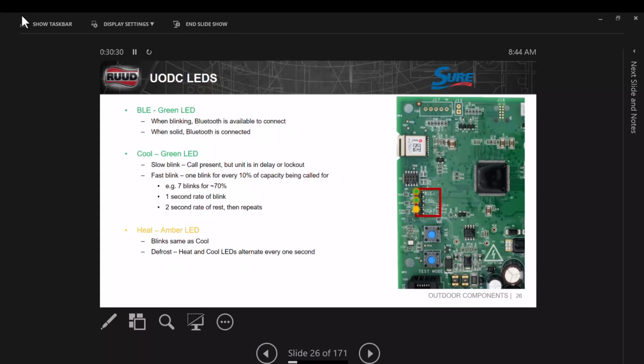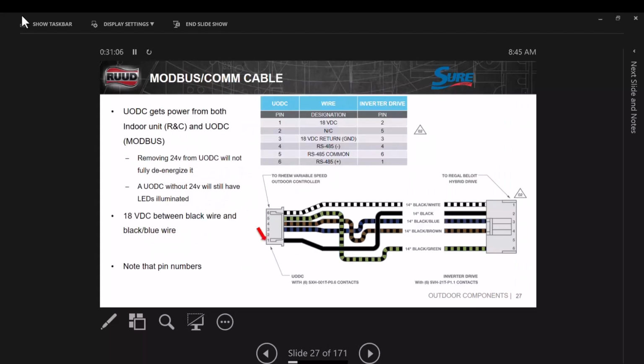The next green light is the cool light, and one blink for every 10% capacity. So every 10% capacity, it's going to blink. Let's say 7 blinks, 70%. And you'll see on the chart what stage that'll be in here in a minute. The amber light is just like the cool light. It's the heat light. It does all the functions that the cool light does, just in the heat mode. So if we're going to do any diagnostics on this unit, this is an important chart. I'd get your phone out and take a picture of this screen, because it's always good to have that information right in front of you whenever you need it. I'll leave it on the slide there for you to do so.